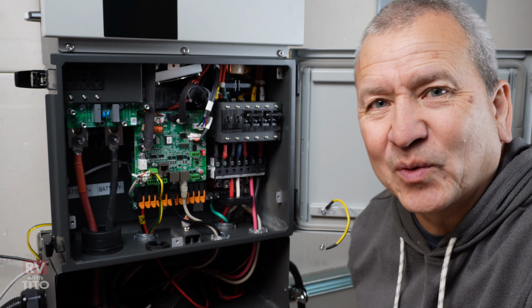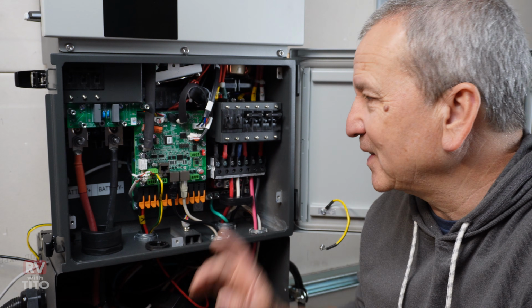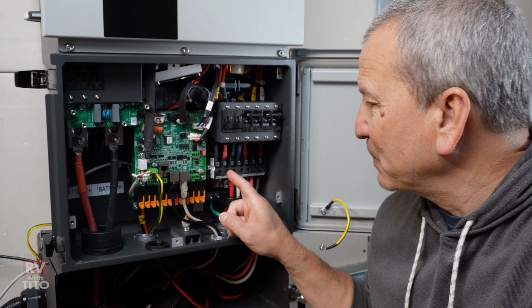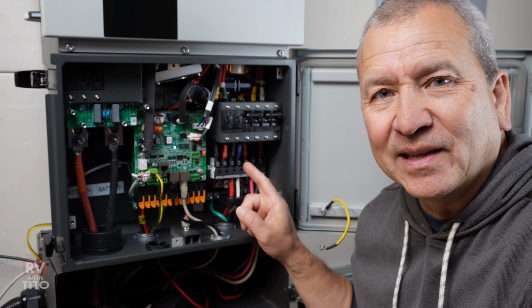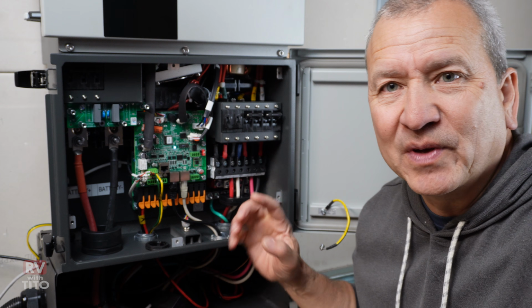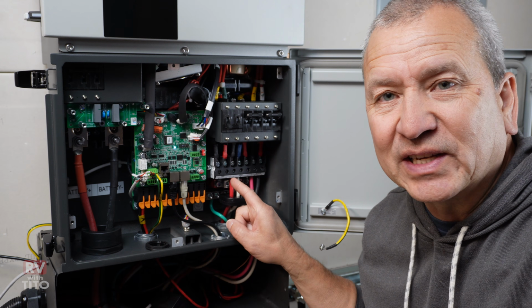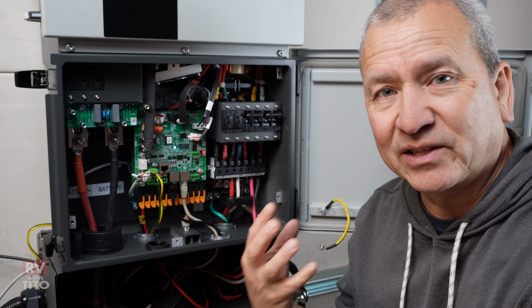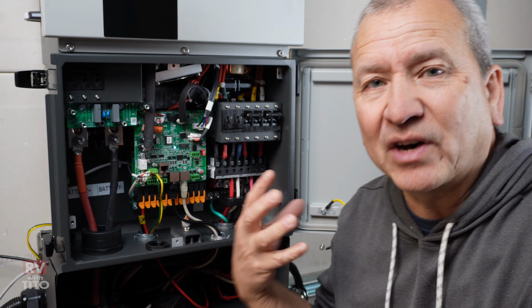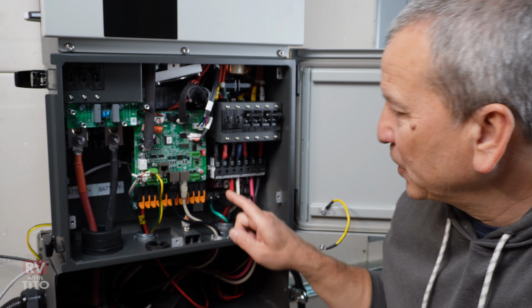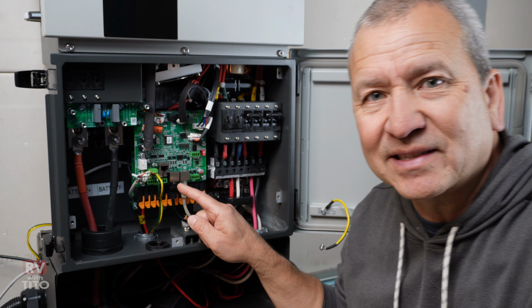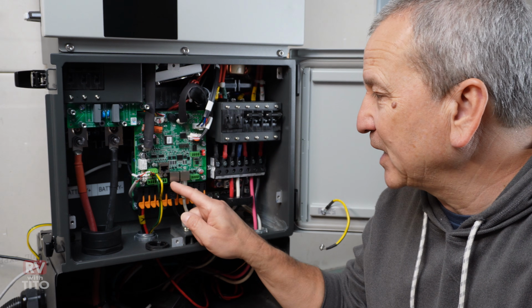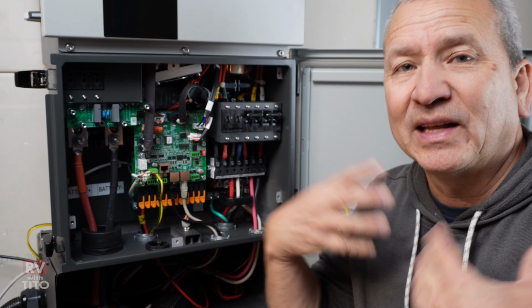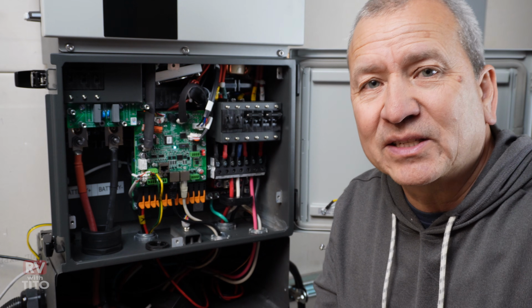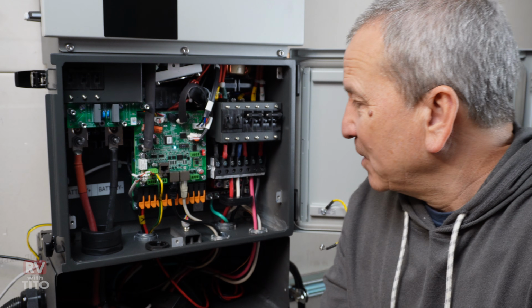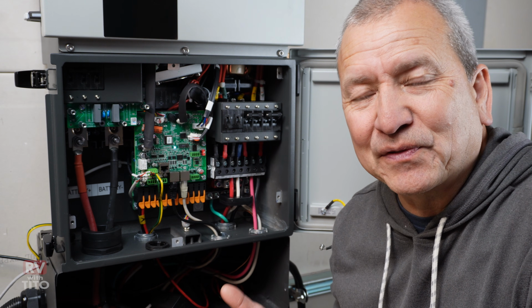This is really one of the cool features that I think this inverter has, which is this multi-purpose input output for the generator. So you have multiple ways to use this. You can use it to connect a generator, and if you have auto start capability on the generator, you can use the dry contacts here and connect those wires here, and it can automatically start and stop a generator. But you can also use it for other things.